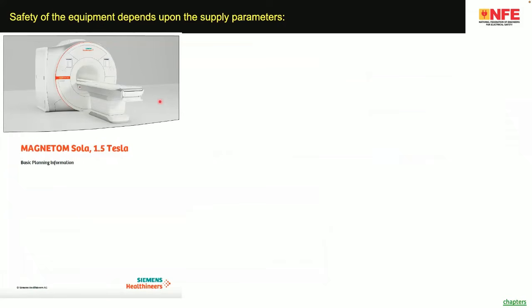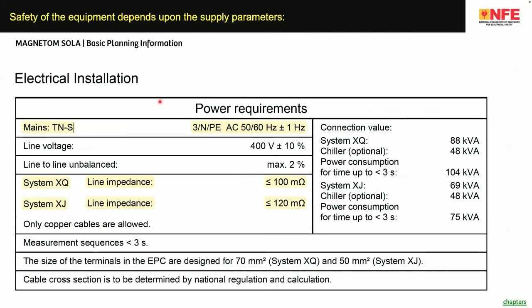Example, Siemens. The catalog says, the manual says it is suitable for a TN-S system, three-phase, N and PE system, and the line impedances are very much mentioned. If you are installing the same machine in a location without complying with the highlighted parts like TN-S or the line impedance, you will be in trouble.